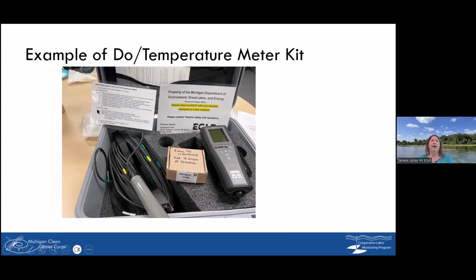This is a quick start guide, to remind you of the different steps when you're going out to take a reading. And then you'll have a cable that's been marked with depths that you need to use for your data sheet. And it'll come with an extra DO, dissolved oxygen membrane, but you very rarely will need to use this extra membrane. Like I said, we have about 44 meters, and every year maybe one or two have empty boxes where the new membrane was needed.